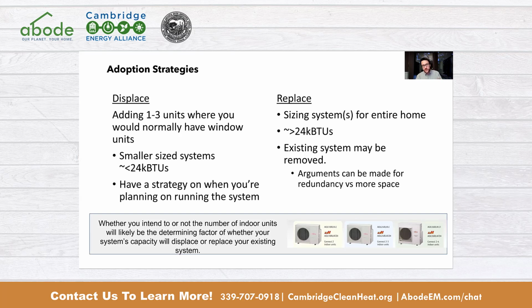But these systems in Cambridge, which typically has smaller footprints, and there are a lot of condos, as we saw in the poll, once you're sizing mini split systems or heat pump systems and you're reaching that 24,000 BTU mark, which the HVAC installer would say is 2 tons, you're really close already to likely having enough horsepower, enough capacity, that you will not need your existing heating system. So in this type of case with replacing it, if you're already looking at the number of indoor units and you're already at 24,000, you're probably really close to having enough capacity for that heat pump to be 100% of your heating load.